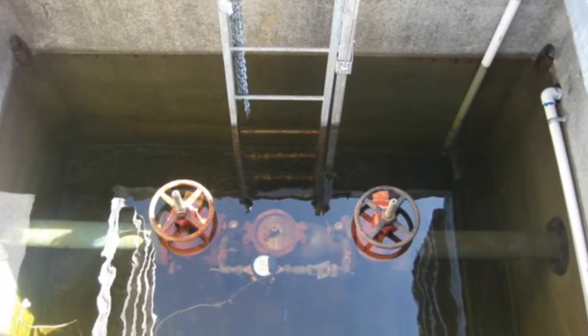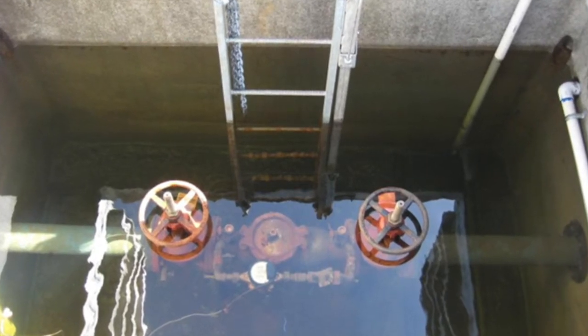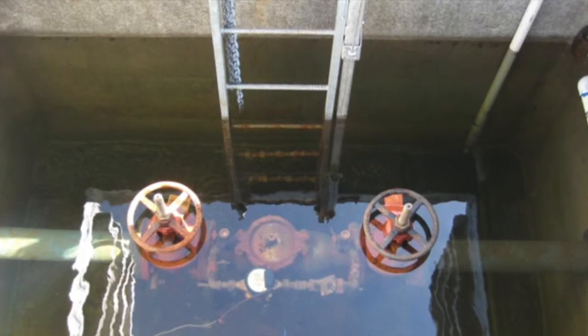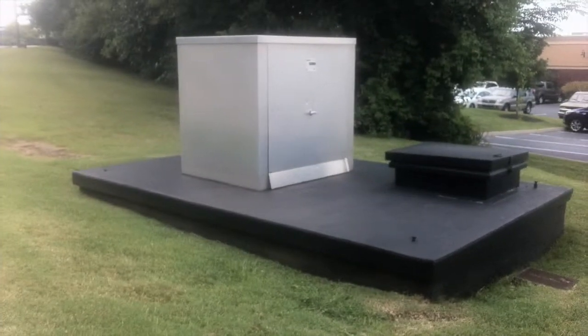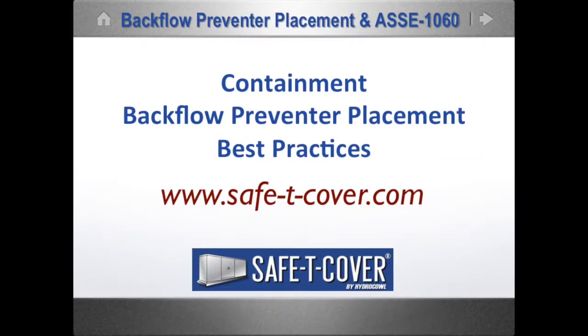Because of the changing demands of containment backflow preventers, it will soon be clear that the subterranean vault is the most expensive option available to a designer, because of the probability of an RPZ retrofit in the future. Learn more about best practices in containment backflow preventer installation at safe-t-cover.com.